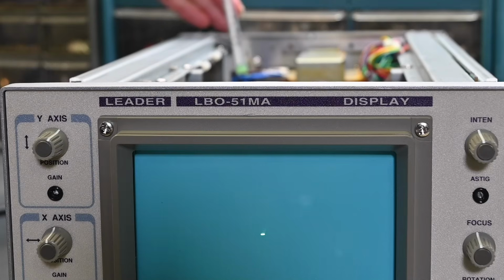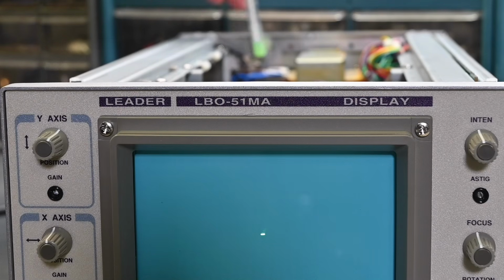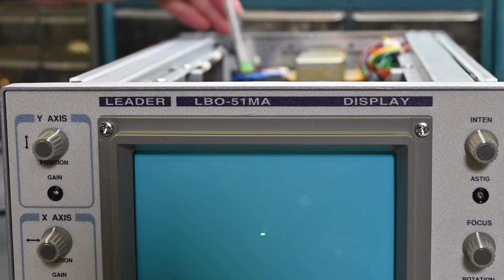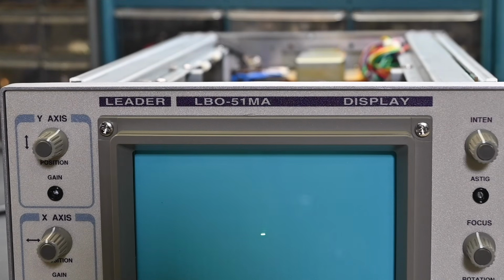So what I need to do is move this wiring down away from this BNC connector, because right on the back of the BNC connector it's not shielded, but it is a shielded cable once it's connected and runs off of the BNC. So this definitely needs to have the wiring rerouted and moved down because it's way too close to that BNC connector. So let me reposition that and see if it takes care of this problem. But it definitely looks like it's picking up some noise and interference, 60 hertz hum basically. And it's very, very sensitive on the input. And the input is high impedance, and of course it's floating right now. And it's just making it pick up that noise. So I'll reposition the wiring. Let's see what happens.